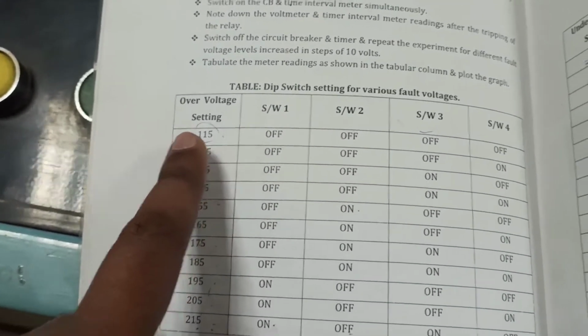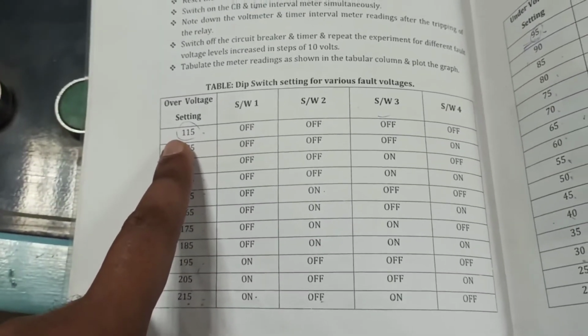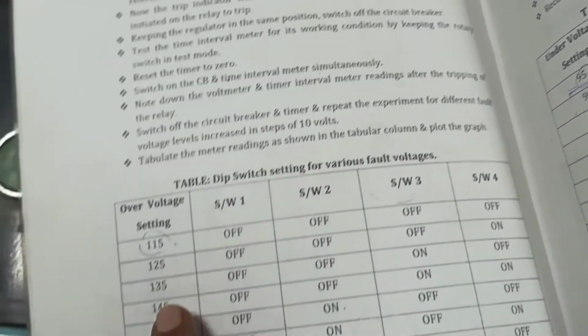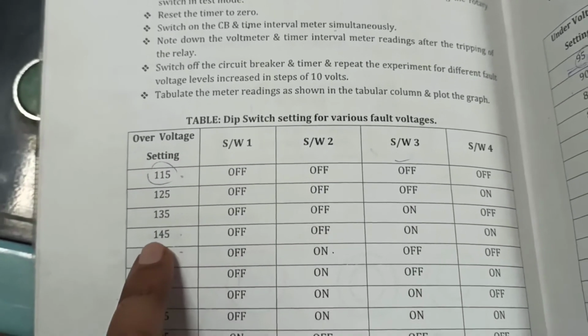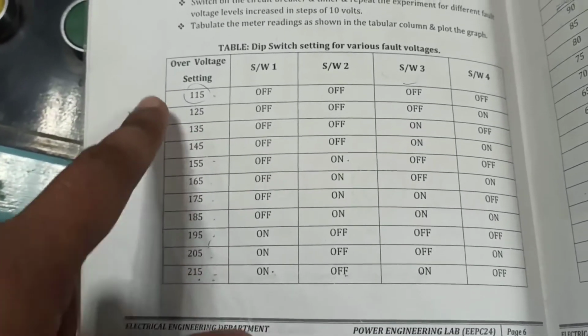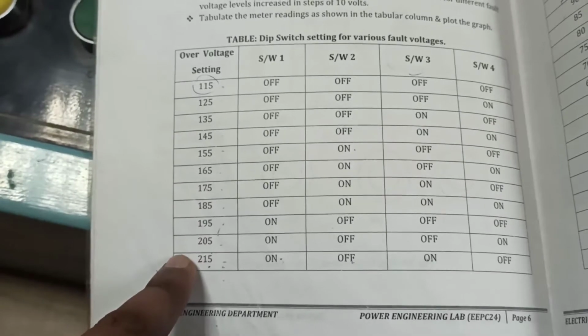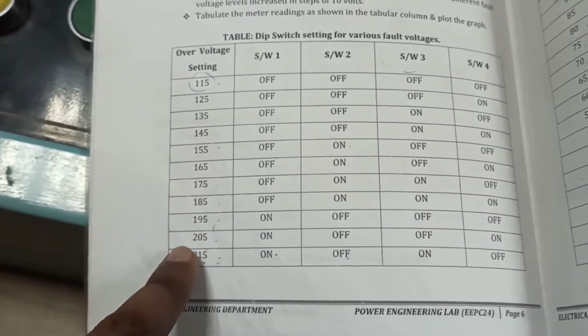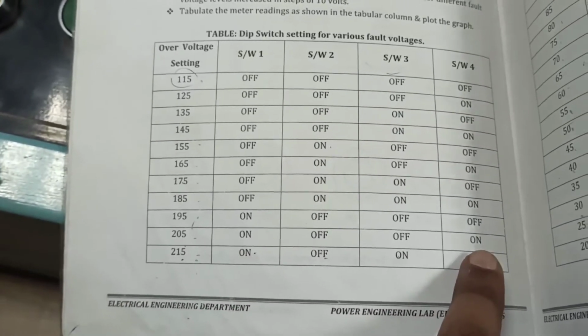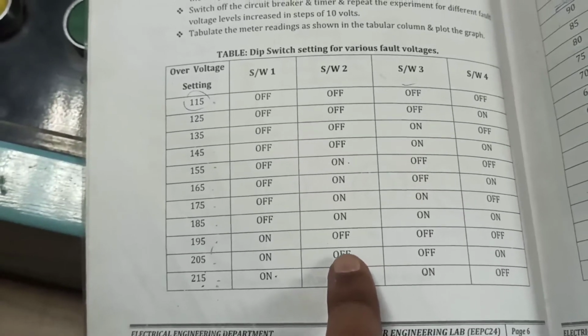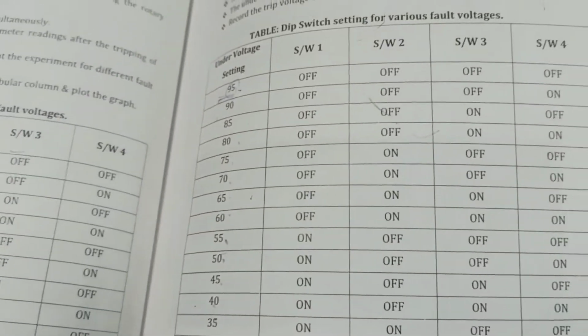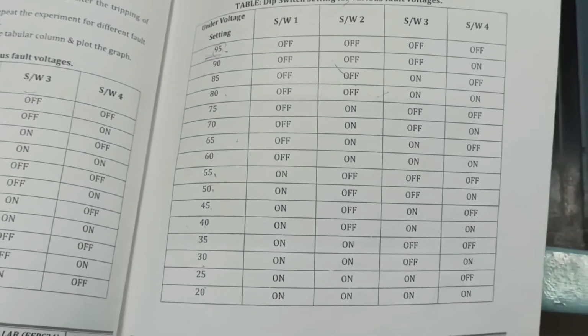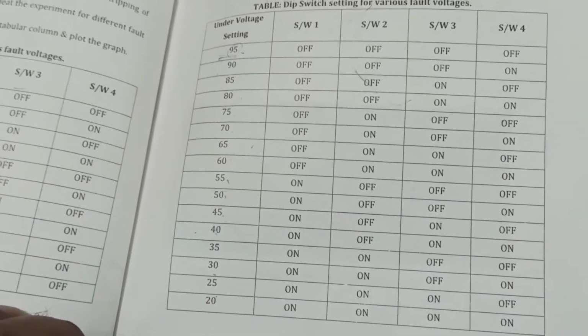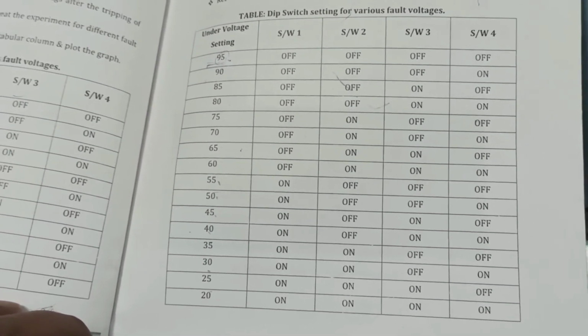So this is for over voltage. When all the switches are turned off, the reference voltage is 115. This means whenever the voltage goes above 115, the relay is going to trip. As you turn on one switch, it increases to 125. Then for the third switch, 135. So like this you have a reference table here. You can see the different ratings. If we want a reference setting of 205, then this and this switch should be turned on and the rest of the switches turned off. So this is for over voltage, and similarly you have it for under voltage. It is the same kit and the same relay, but the settings of the relay are different. So the same relay will work for over voltage as well as for under voltage.